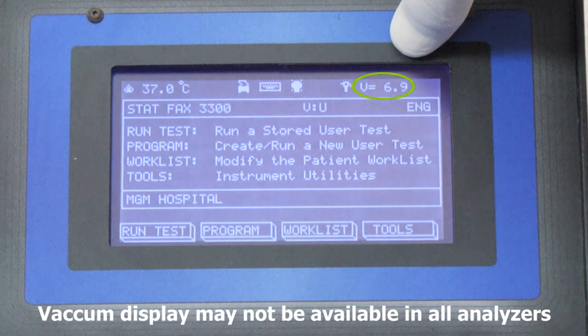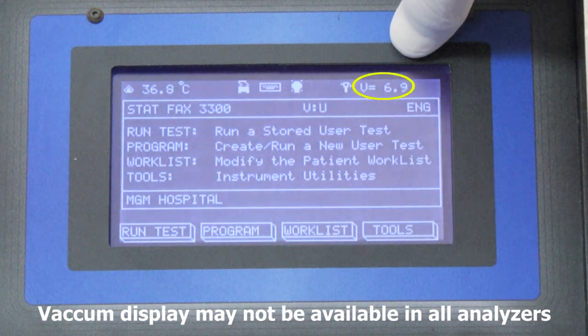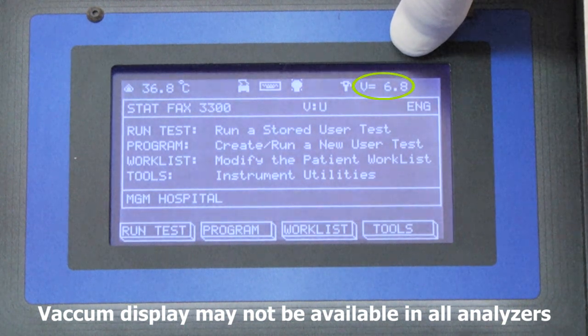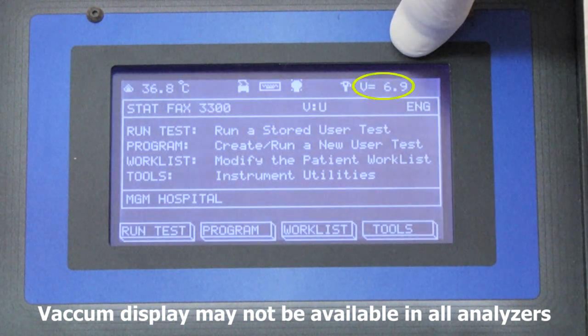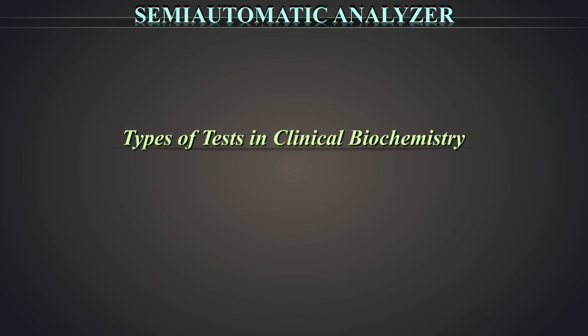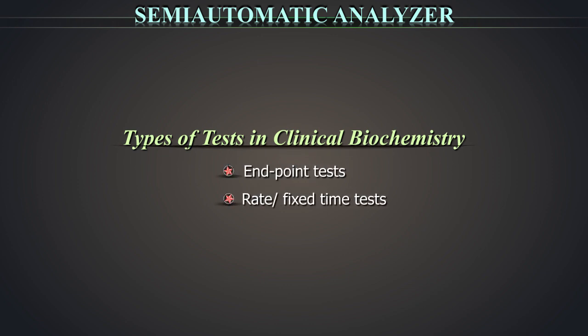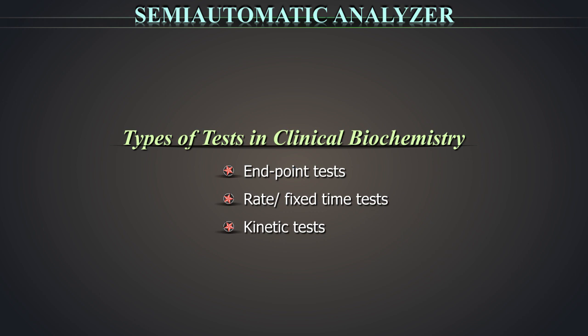Vacuum should be maintained at 6.9 ±1. This is very important for sample aspiration and analysis. If the vacuum is not maintained, immediately switch off the equipment and call the technical support team. Types of tests in clinical biochemistry: endpoint tests, rate or fixed time tests, and kinetic tests. We will discuss one example of the endpoint test in this tutorial — the measurement of glucose by glucose oxidase peroxidase, i.e. the GOD-POD method.